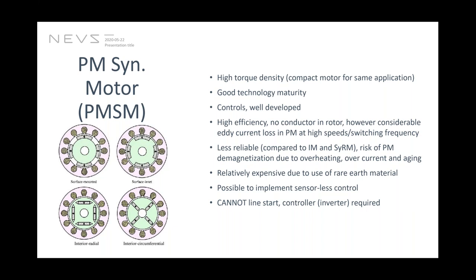The one drawback I can name for this motor is that it is slightly less reliable, because the permanent magnets are very sensitive to heat and overcurrent and will deteriorate over time. Those are the things that make it less reliable. These motors are relatively expensive because of the rare earth metal, and the price of rare earth metal fluctuates. So you cannot even fix the cost, and almost all of it is controlled by only one country, China. So market turbulence is also a big factor there.